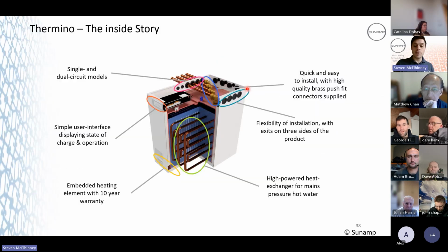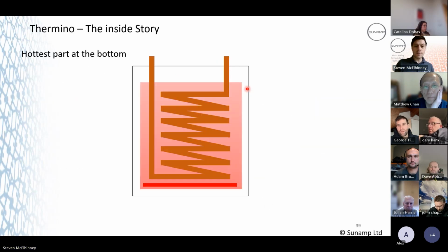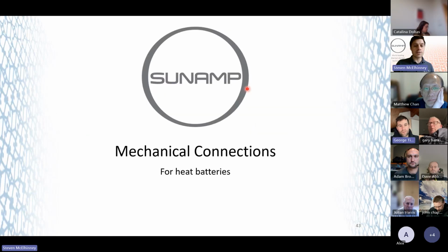I mean, the amount of times I've had to turn TMVs down for customers in a house, and then you start asking them, "Oh yeah, my hot water is quite hot." Like, well, turn it down. Just turn that dial, because it's up to them. Oh, and always get them to check it as well, to make sure they're happy with that temperature. There's no point in setting it to 40 if the customer's saying that's not hot enough for me.